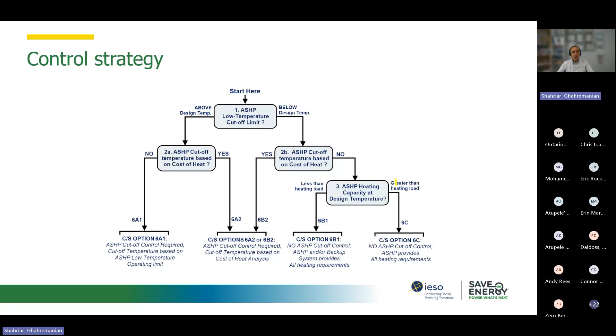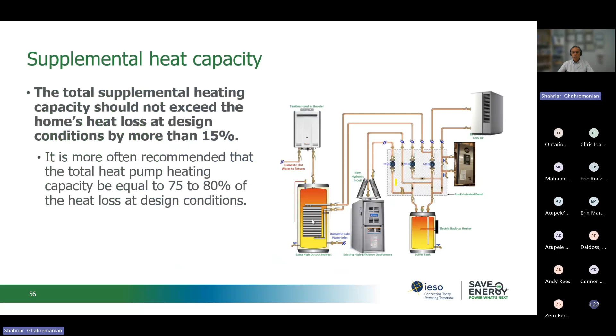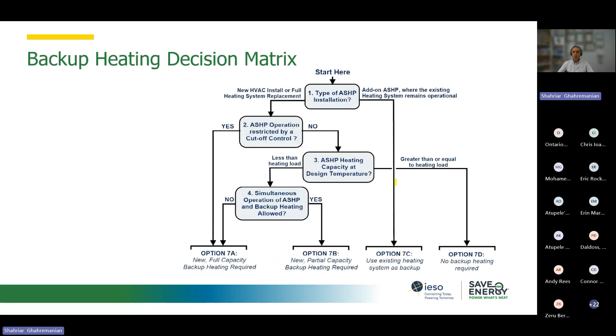So, the total supplemental heat should not exceed the home's heat loss at the design conditions by more than 15%. We talked about it, and that's typical based on the industry. The industry and the trades or contractors follow this rule when they do that. And also the same decision matrix applies for the backup heating when it needs to be supplied.